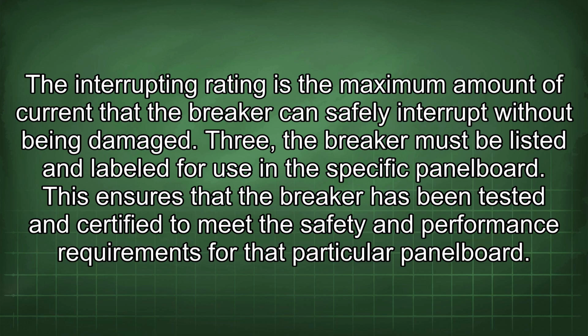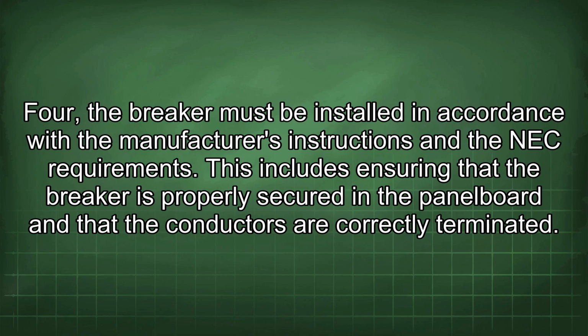3. The breaker must be listed and labeled for use in the specific panel board. This ensures that the breaker has been tested and certified to meet the safety and performance requirements for that particular panel board. 4. The breaker must be installed in accordance with the manufacturer's instructions and the NEC requirements. This includes ensuring that the breaker is properly secured in the panel board and that the conductors are correctly terminated.